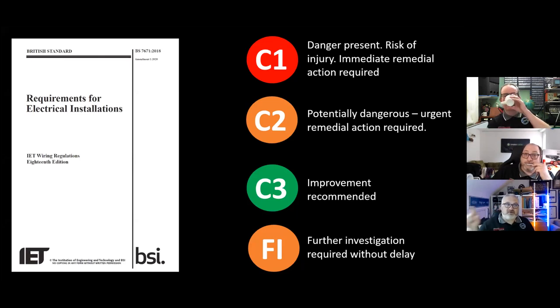Now, I'm going to be really controversial here, and I'm not going to read the comments because I'll probably get those. FI, I only ever want to see FI on a report where I'm time limited. This is my professional opinion, and that is all down to the extent and limitations of the inspection. So you'd say an FI would always be a result of an operational limitation, like time. Yeah, and it can be something as simple. On the domestic front, you may find that you spend 2.5 hours on one lighting circuit, so you have no choice but to FI the installation. It's purely time centric. I would rather spend the time qualitatively pulling apart a lighting circuit, making sure it's fault free, or that I'm not giving rise to danger for that installation, and tell the customer that as you're going along. So for me, FI is more of an extension of time. I know others will look at it differently.